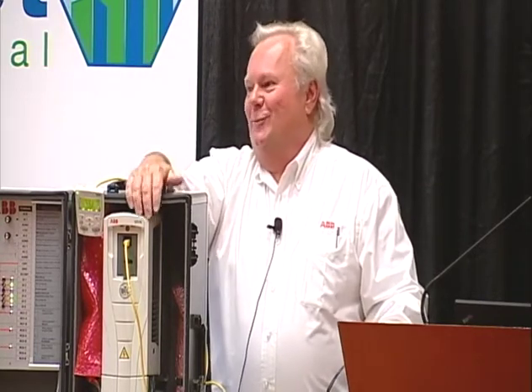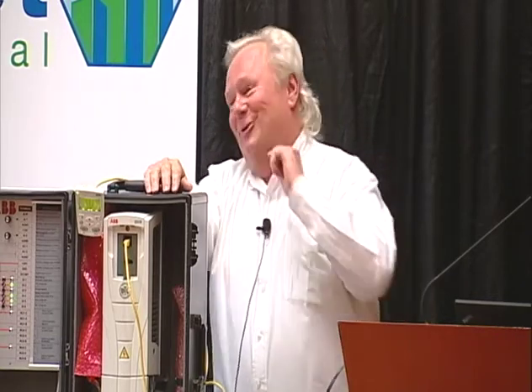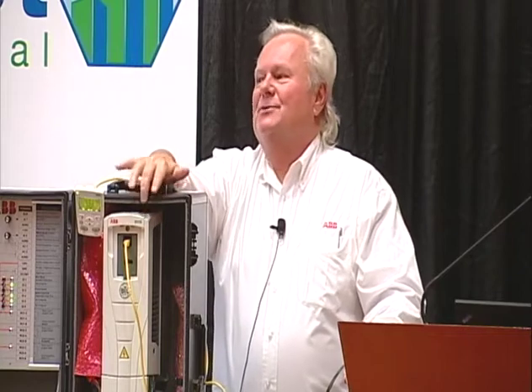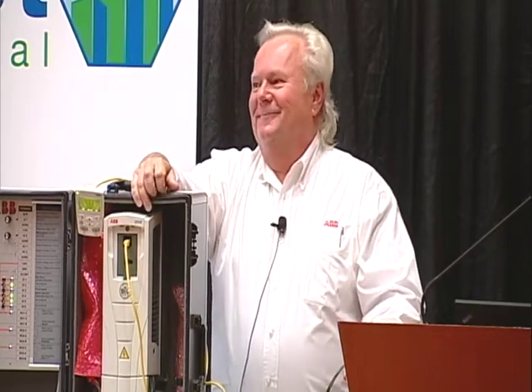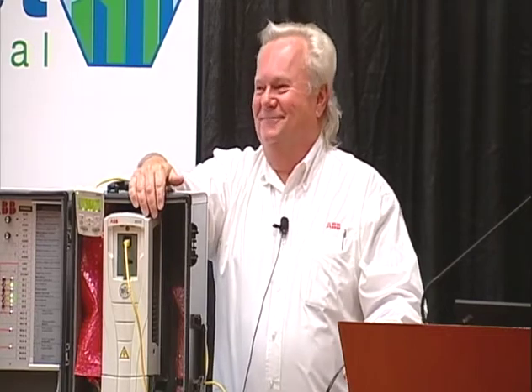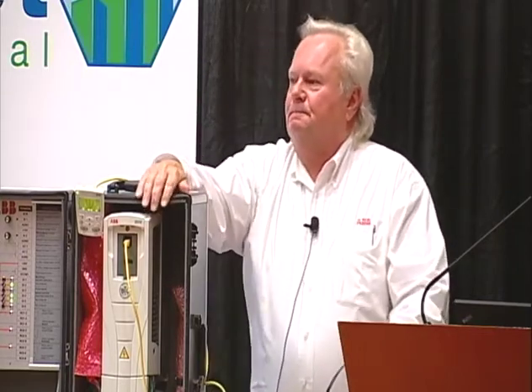The bypass itself has five more relay outputs in it that are all exposed to the BACnet system and can all be controlled. So 5 plus 6, we've got 11 relay outputs. We've got tons of digital. What we're short on is analogs. And there is no analog expansion card for this product. So that's part of where we're going. Next generation is gonna have stack up and more PID loops and all sorts of stuff. Yeah, but our whole goal, or one of our goals, I should say, in this building automation process is to not require external hardware to be able to do the brains on board. But yes, that's still a possibility.